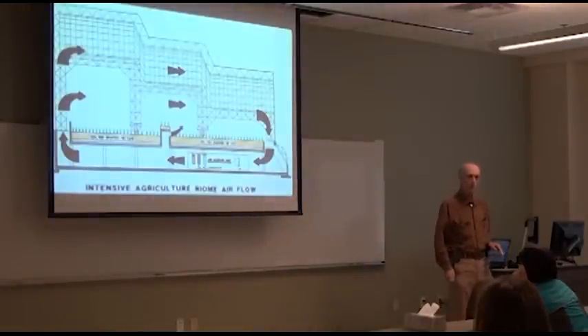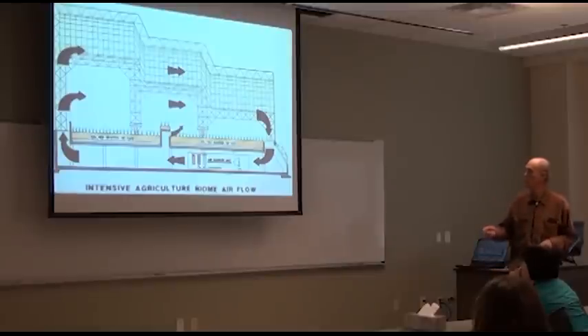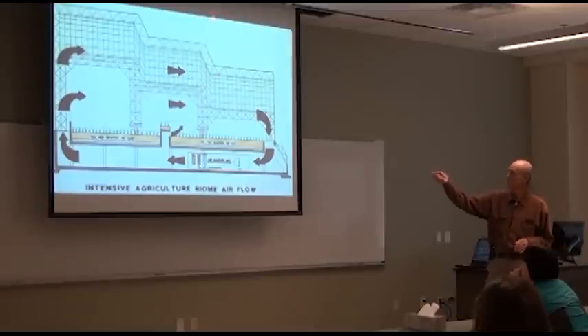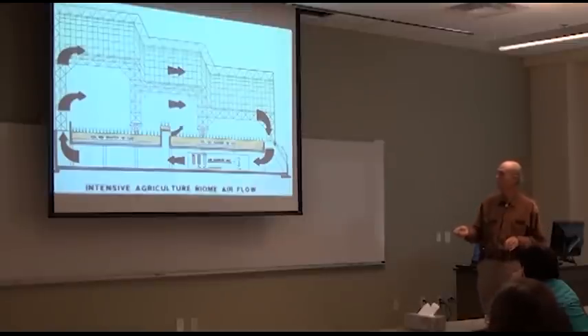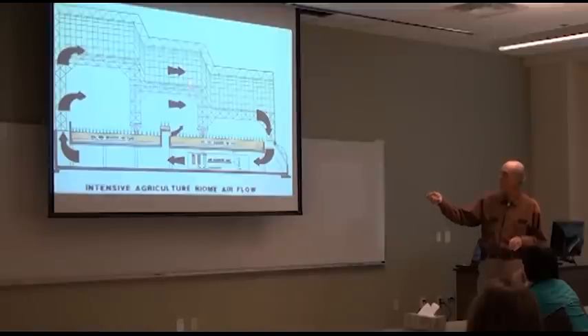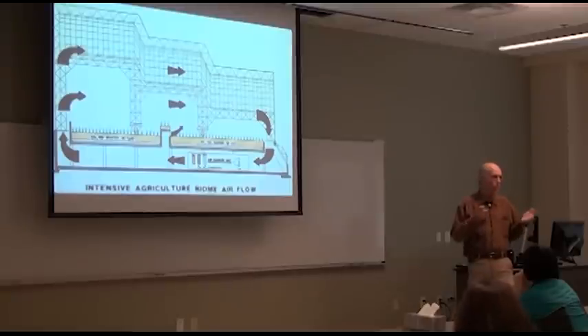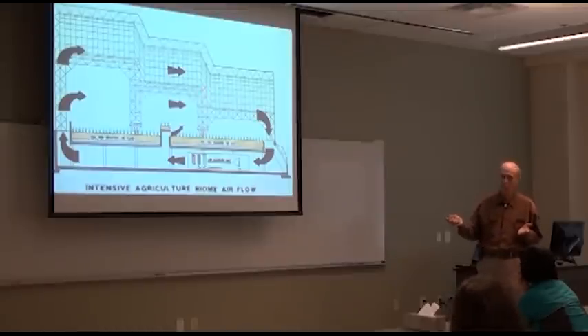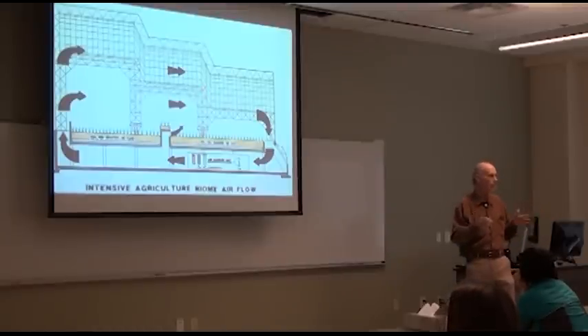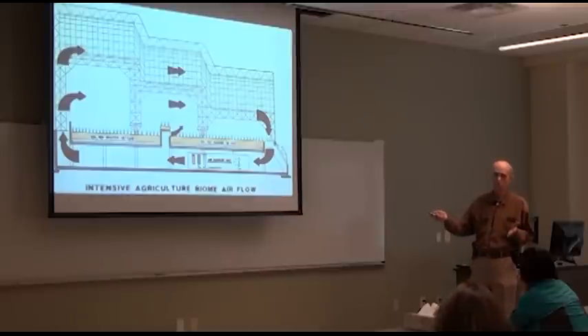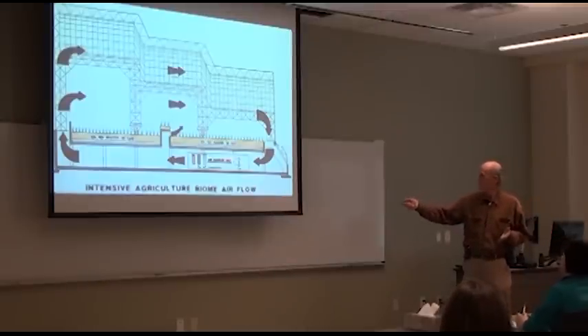And here is how heating and cooling worked in Biosphere 2. Sunlight is streaming in and making the air warmer. Plants are evapotranspiring and moisture is coming into that air. You have to remove the moisture and you have to cool the air in order for this process to be sustained. If the moisture just went into the air indefinitely, it would become saturated, 100% humidity, evapotranspiration would stop, and the plants would die. So the air handler is in the basement.